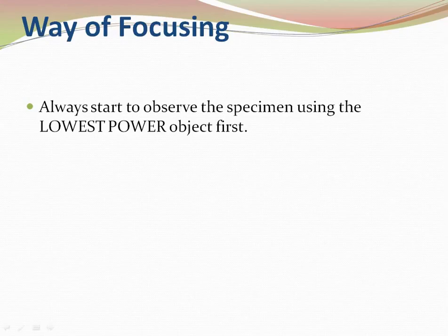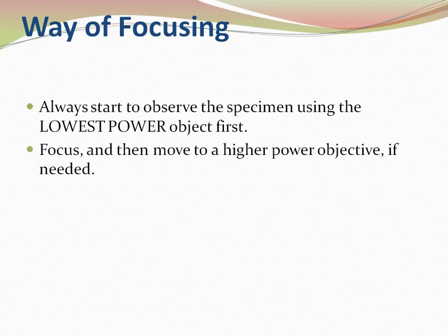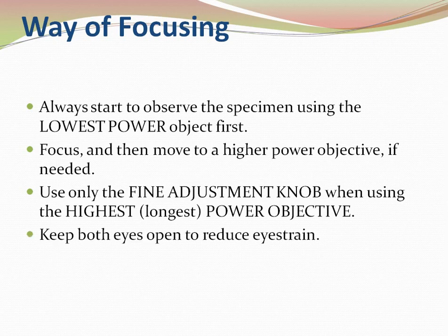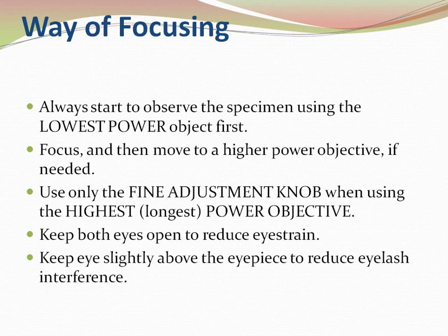How to focus the specimen: always start by observing the specimen using the lowest power objective first, then focus it, and then move to a higher power objective according to your need. Use only the fine adjustment knob when using the highest power objective. Keep both eyes open with a binocular microscope to reduce eye strain. Keep eyes a little bit away from the eyepiece to reduce eyelash interference in the field of vision.